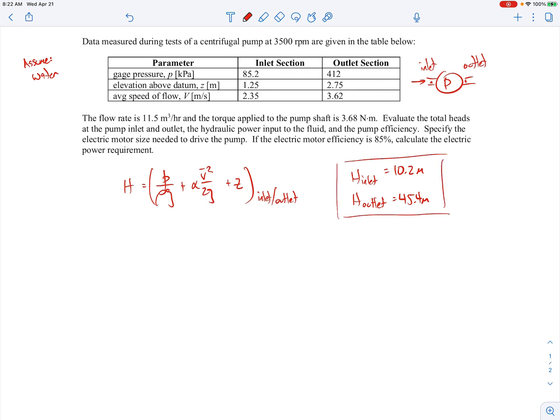There's clearly a head rise between the inlet and the outlet. These head calculations are based on the gauge pressure that's given. Gauge pressures are typically used when analyzing pump systems because you're dealing with pressure differences. It really doesn't matter whether you use absolute or gauge pressure, because when you're interested in the delta H — the head rise across the pump — the atmospheric pressure cancels out when you take the difference.